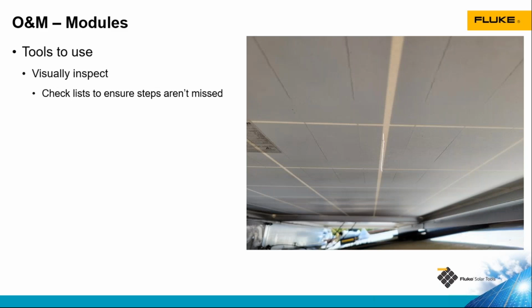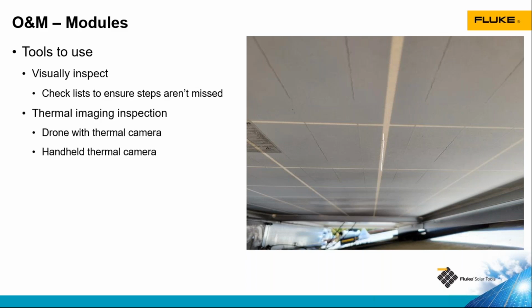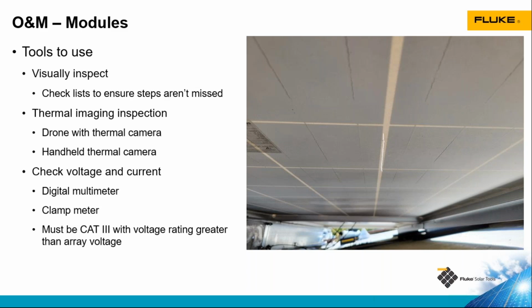Visual inspections, again, a trained inspector having a good checklist is really key. Thermal imaging can be done with a drone with a thermal camera or a handheld thermal camera. We can also use multimeters and clamp meters to check voltage and current, as long as they have the proper category and voltage rating. If we're doing DC testing in the array, that would need to be a category 3 tool with a voltage rating higher than the voltage at which we are testing. If we're doing testing on the AC side of the system, close to our point of interconnection, that would be a category 4 tool, again with a voltage rating above what we'll be testing at.